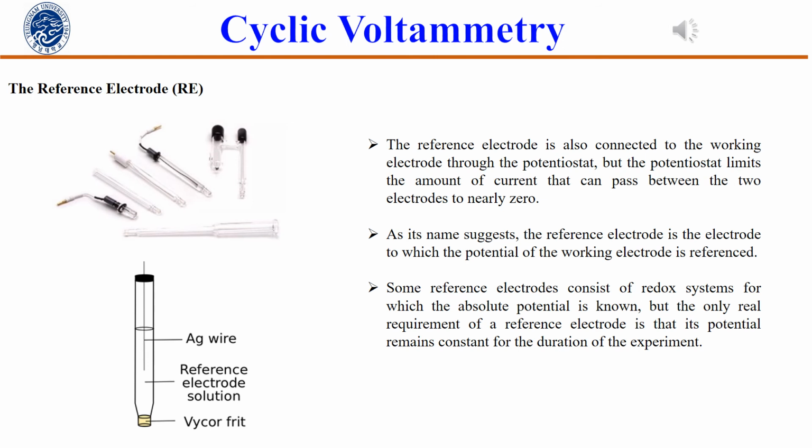We should take more care to prevent the Vycor frit from drying out, which causes the electrolyte salt to crystallize in the pores and render it unusable. Before doing the test, we need to check the frit by attempting to squeeze liquid through it using a pipette bulb. If fluid doesn't filter through easily, it should be replaced.